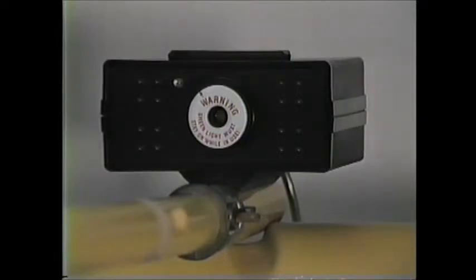The HLS 5 will operate for approximately eight minutes from the time it is first switched on until it turns itself off. This eight-minute timer will reset itself every time the on switch is depressed and every time the unit senses a voltage. It would therefore stay on continuously if placed on an energized line.